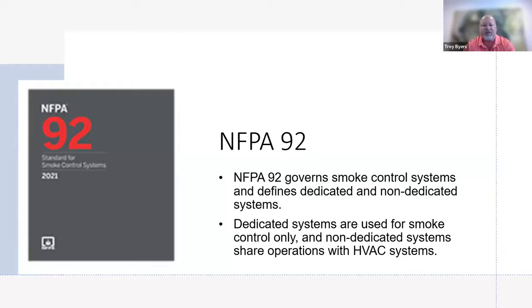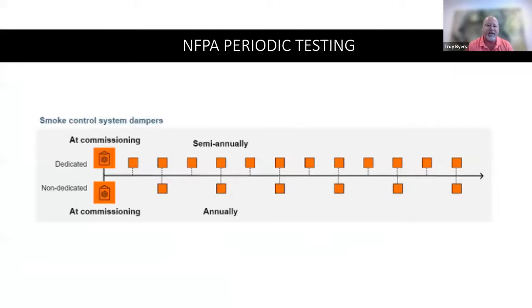So in NFPA, we'll look at one of the standards that Larry mentioned earlier. NFPA 92 is what governs smoke control systems. In my section of the presentation, we're going to talk a little about systems beyond individual components, such as fire and smoke dampers. The definition in NFPA 92 gives us dedicated versus non-dedicated systems. A dedicated system is used for smoke control only, whereas a non-dedicated system also shares operations with HVAC systems. We'll give some examples of that.